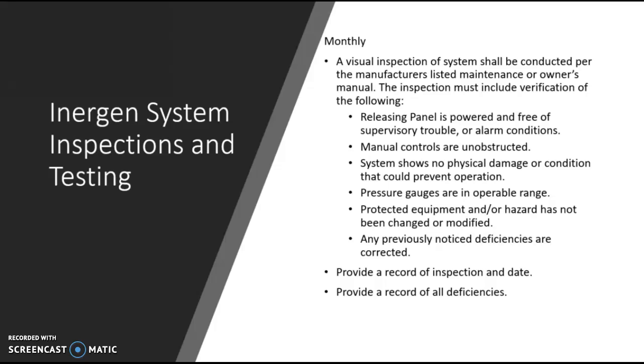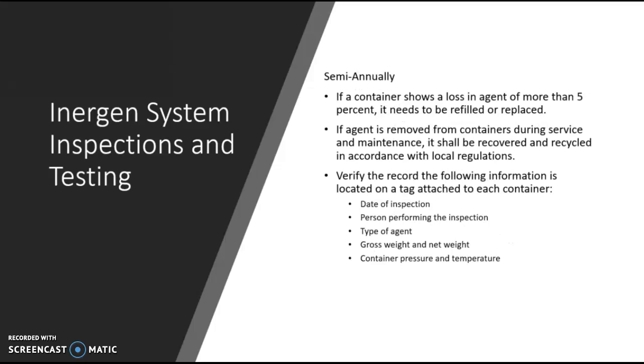We want to make sure the pressure gauges are working in proper range. Protected equipment or the hazards have not been changed or modified. So whatever it's serving, in y'all's case, we want to make sure that the MRI equipment is operating accordingly, to make sure that your devices are working and protected from a fire. Provide a record of inspection and date, and then provide a record of all deficiencies.